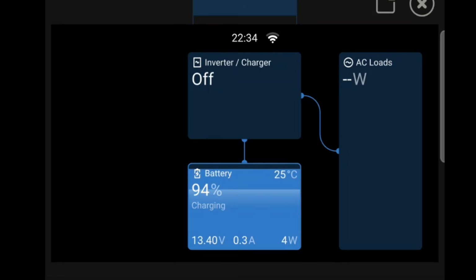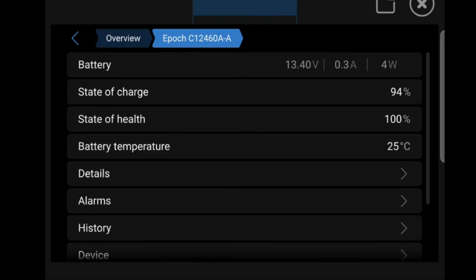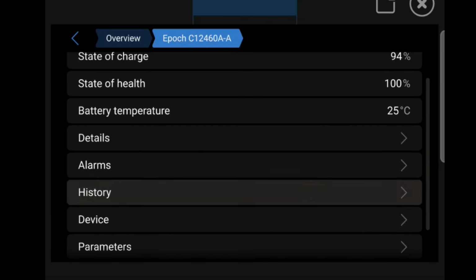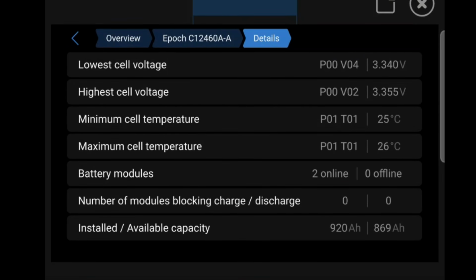Let's click on the battery tile for more information and look at details. We have battery modules online: 2 online, 0 offline. Number of modules blocking charge or discharge: 0. If there was a code or warning in either battery, it would show 1 or 2 depending on what was blocking charge or discharge. For installed and available capacity, we have 920 amp hours installed and currently 869 amp hours available, so everything looks good there.